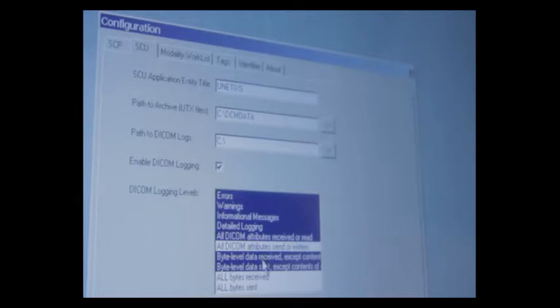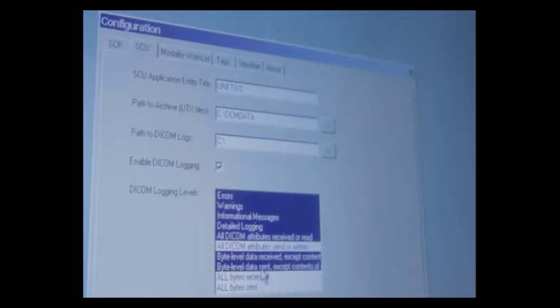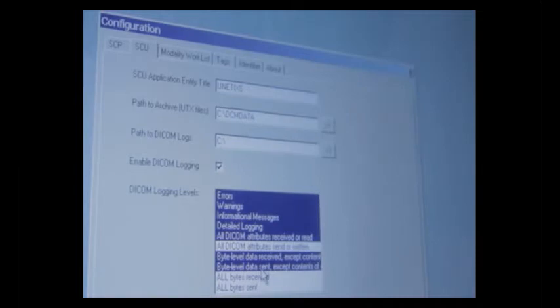...written, byte level data received, and byte level data sent, this will create a log file that will tell you if the communication is failing exactly which end the problem is on, whether it's a setting on our side or a setting in your DICOM that's not functioning.